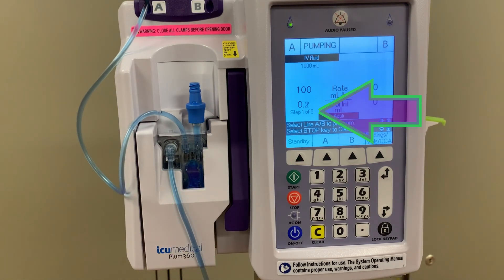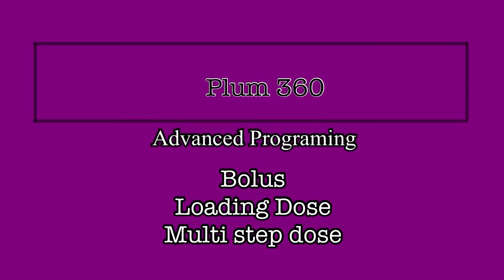On our infusion screen, you can see it displays what step of the program you are on and how many total steps were programmed. These advanced programming options will not be something you utilize for most infusions, but when a medication has a more rigid administration regimen, or if you find yourself needing to bolus from a medication bag, knowing how to properly use your Plum360 can make life a lot easier.